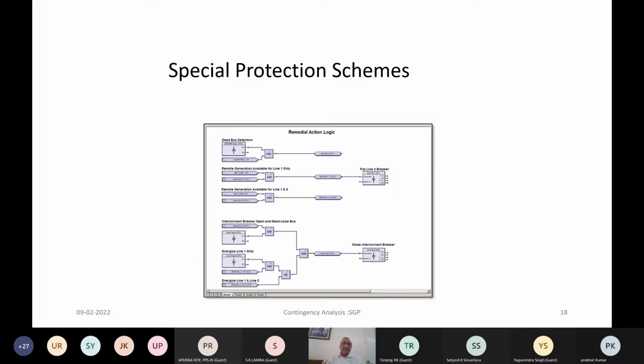So this function, which is part of the excitation system, is called power system stabilizer, and all the units which are of the said size, that is 100 megawatt and above and 250 megawatt and above thermal units, they all need to respond to these oscillations so that these oscillations can be damped out. That is the purpose of power system stabilizer.